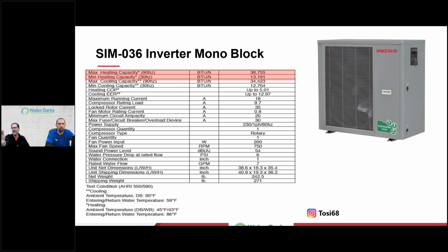Here it is, heating COP, asterisk. Be aware of what that little star means. It says here up to 5.01. Again, a COP of 1 is 100%. A COP of 5.01 is over 500% efficient. At what temperature? Ambient temperature, dry bulb and wet bulb, 45 and 43, and an entering return water temperature of 86. Is that a reality of an application that you're going to do? Understand that anything electric is already 100% efficient, at 120 degree water, okay?